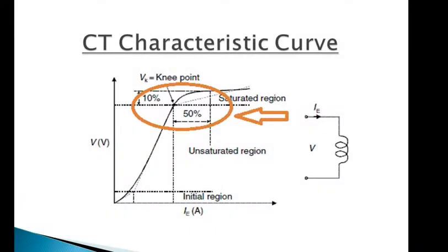If we look at the CT magnetization curve, we can see that the CT will get saturated after reaching the knee point voltage. As per IEC, knee point voltage is defined where a 10% increase in applied voltage will raise the excitation current by 50%.